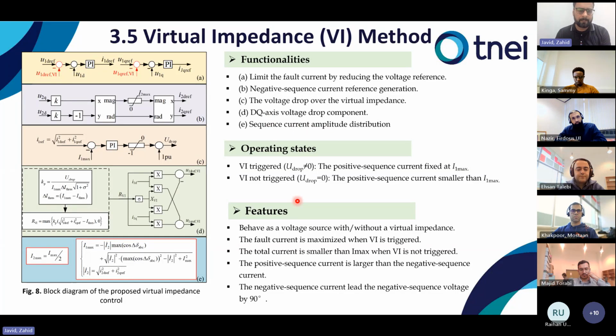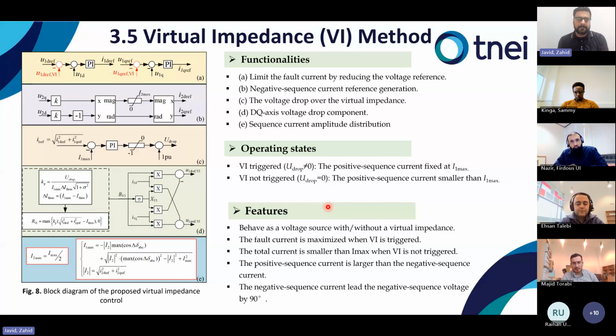The main features are that it behaves like a voltage source with and without virtual impedance, and the fault current is maximized when virtual impedance is triggered. If the total current is smaller than Imax, then we don't need to trigger the virtual impedance control. The positive sequence current is larger than the negative sequence current, which is also a requirement of the standard, and the negative sequence current leads the negative sequence voltage by at least 90°.